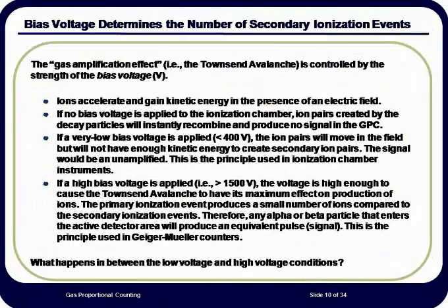The extent of the Townsend avalanche is controlled by the bias voltage applied to the detector. As the voltage is increased above zero, up to about 400 volts, secondary ionization effects are minimal and the resultant pulse size is small. This region of the voltage curve is used for instruments called ionization chambers. If the voltage is increased to approximately 1500 volts, the Townsend avalanche creates so many subsequent ionizations after the initial events that there is no distinction in pulse height between alpha and beta particles.